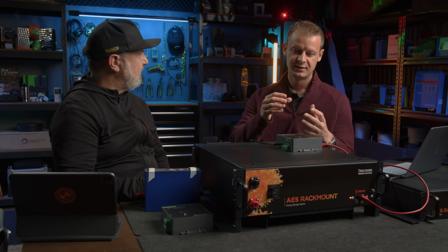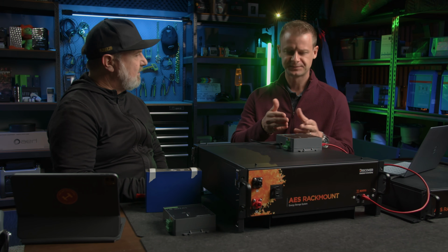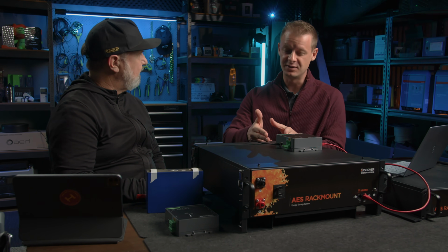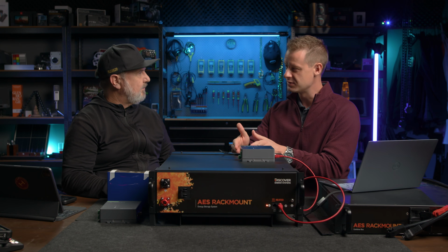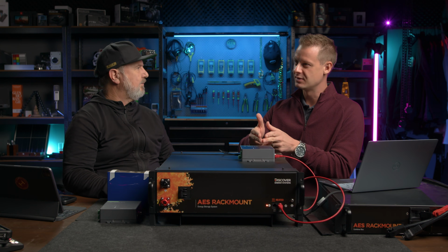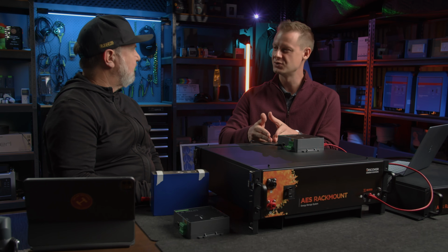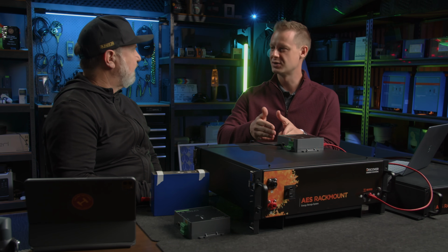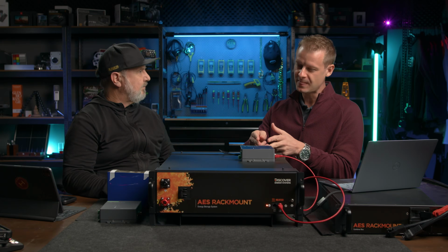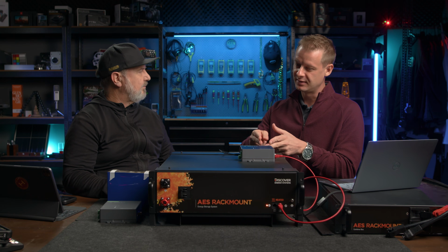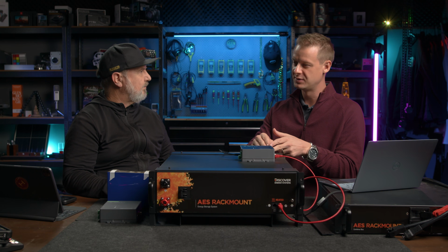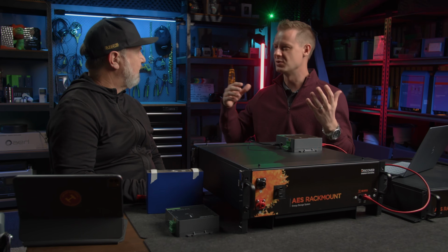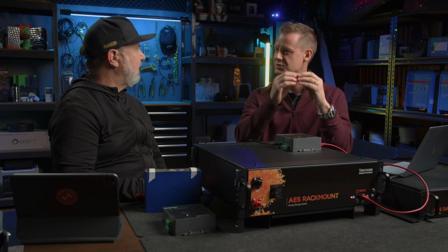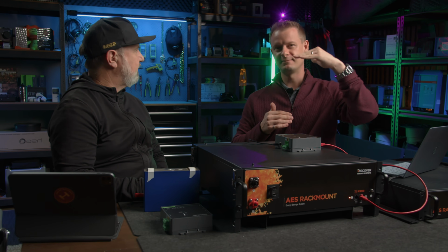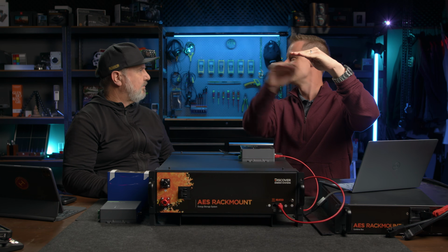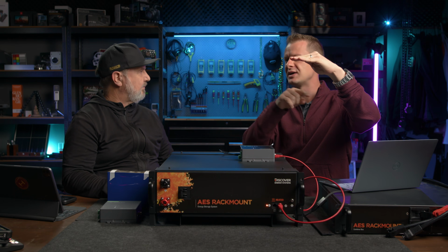With an open loop charge and more prescribed phases in the inverter, you'll see them walk through bulk, absorption, float, and they make that jump from absorption to float based on certain triggers, usually a current-based trigger. In an active dynamic closed loop situation, there's no such thing as bulk, absorption, float — it's just hit my target voltage. If we hit 54.4, stay there as long as you can, and the current will gradually taper.